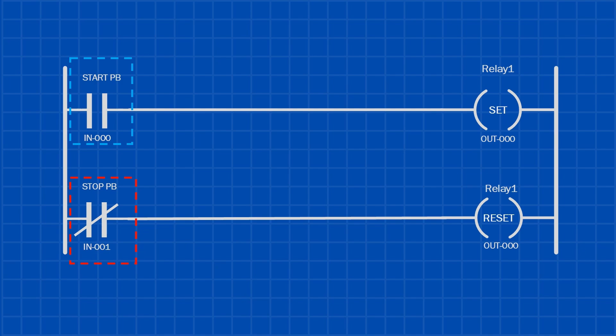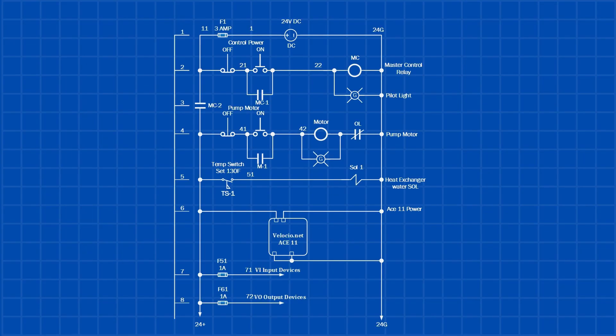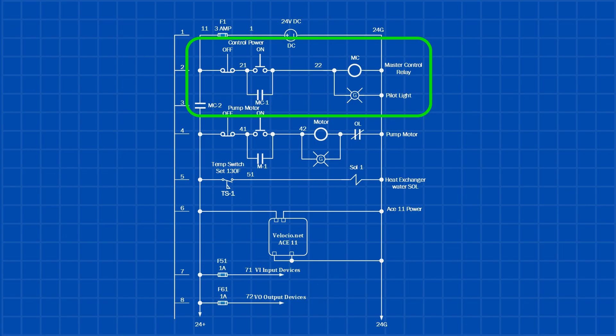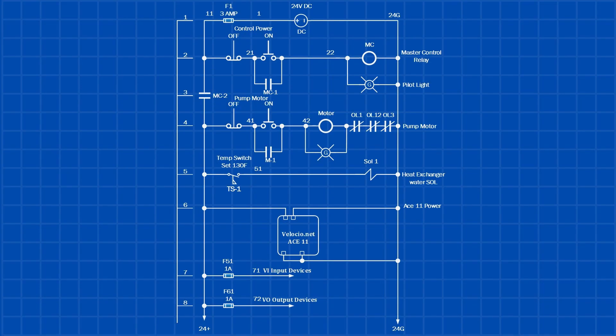Now that we understand what a latching circuit is, let's talk about what it's actually used for. The first common use of a latching relay is in a master control circuit. The latch is used to power up the control panel, with the MC2 contact supplying power to the rest of the system. When the stop button is pressed, the relay turns off and the entire control circuit shuts down.